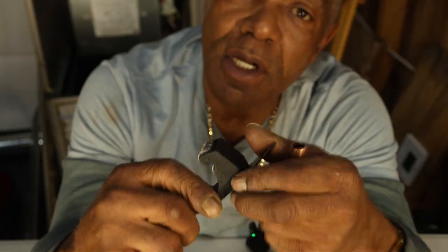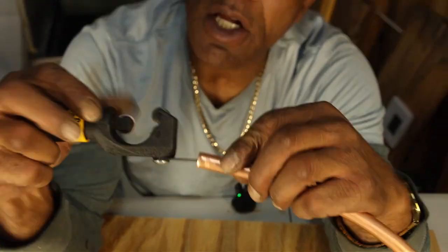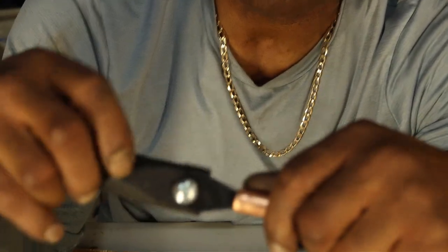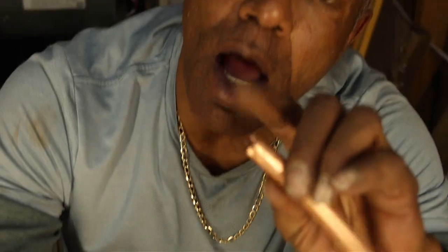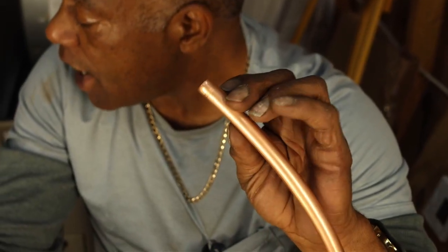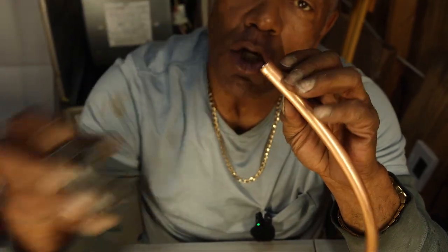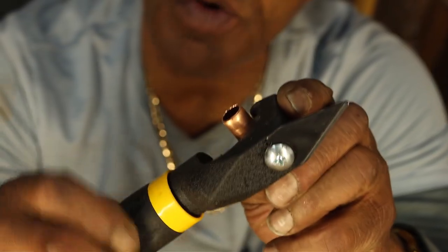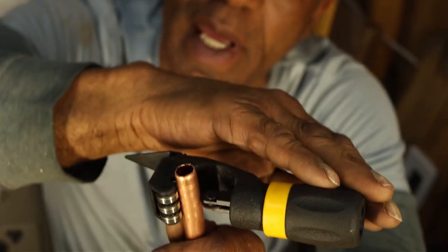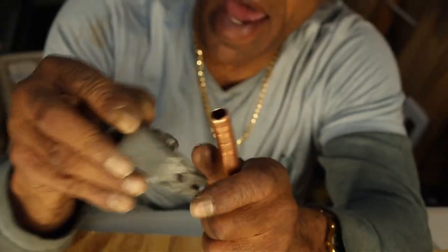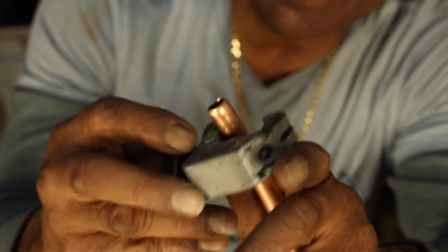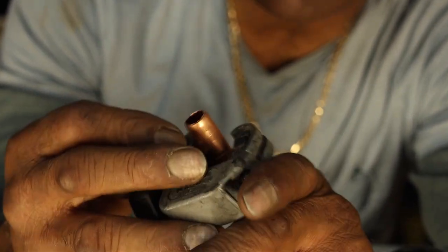This is my tubing cutter. And this would help me clear any shavings that fell off of the copper when it was being cut to make sure my copper is clear. Also, sometimes you need a shorter tubing cutter because the long tubing cutter, when you go to spin it, there may be other obstacles that this long body will hit and not allow you to make your complete revolution. So you may have to have a small tubing cutter that will go into tighter, refined areas.